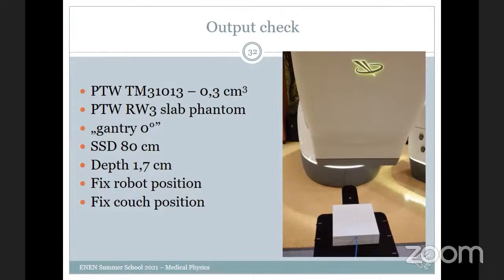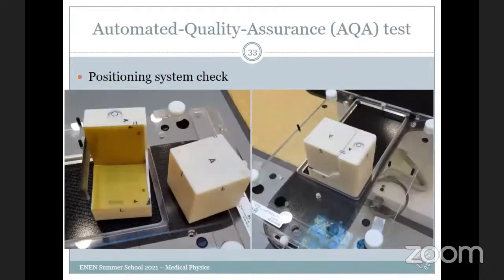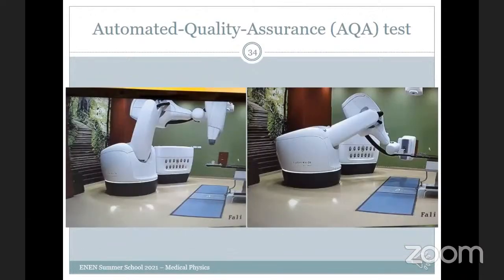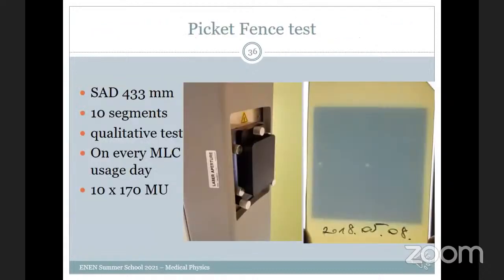We do an output check every morning with a small ionization chamber with a fixed setup, fixed robot and couch position. We check that the delivered dose is equal to the desired dose. We do automated quality assurance, the so-called AQA test, for a very fast and very quick geometrical test. From two directions we check the position of the robot and the imaging system. With the picket fence test every morning we check the stability and the precision of the MLC.